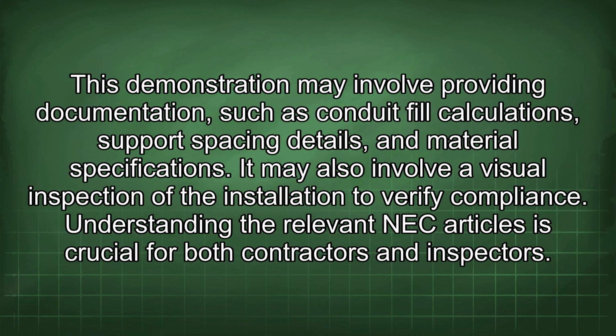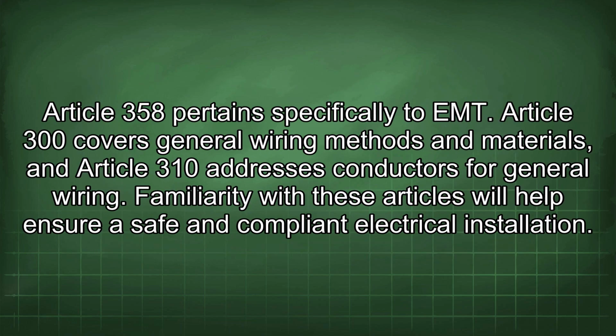This demonstration may involve providing documentation such as conduit fill calculations, support spacing details, and material specifications. It may also involve a visual inspection of the installation to verify compliance. Understanding the relevant NEC articles is crucial for both contractors and inspectors. Article 358 pertains specifically to EMT. Article 300 covers general wiring methods and materials, and Article 310 addresses conductors for general wiring. Familiarity with these articles will help ensure a safe and compliant electrical installation.